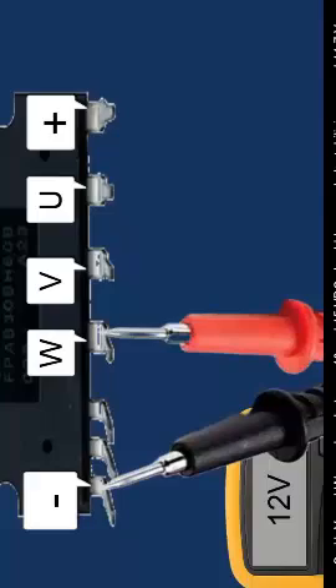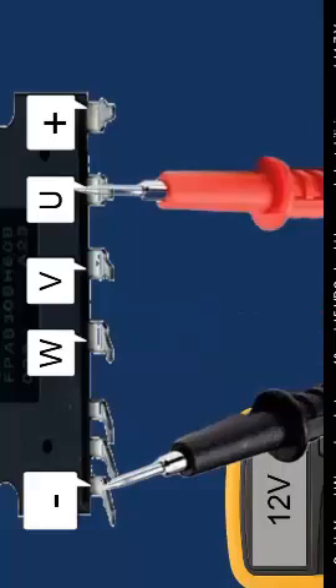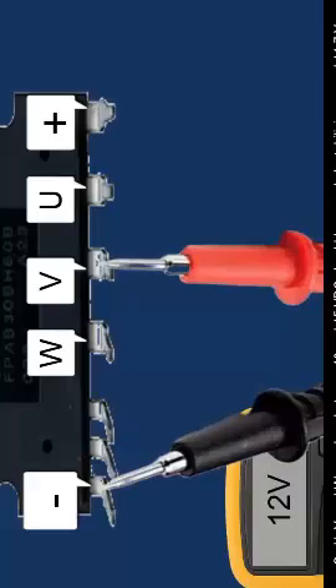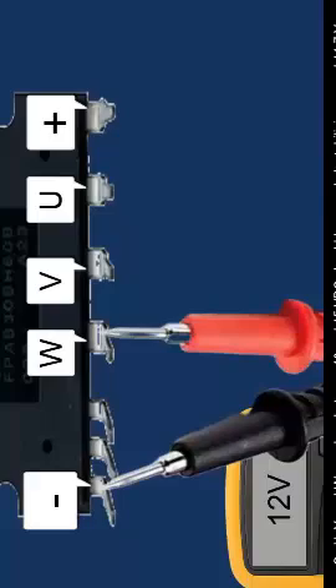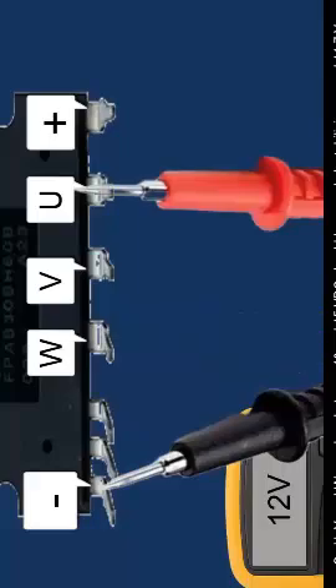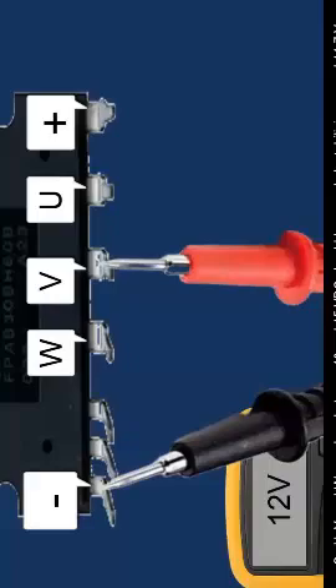An IPM may pass visual and multimeter tests, but when the PCB is powered, the fault becomes evident. For example, if on phase V, instead of approximately 12 volts, 304 volts appears, it means the IGBT of that phase is short-circuited.